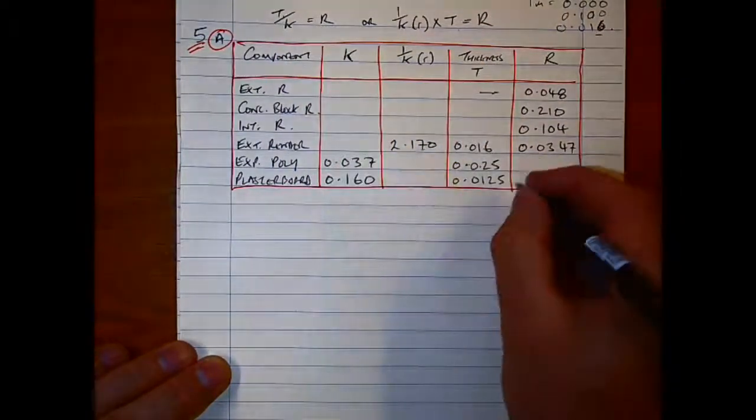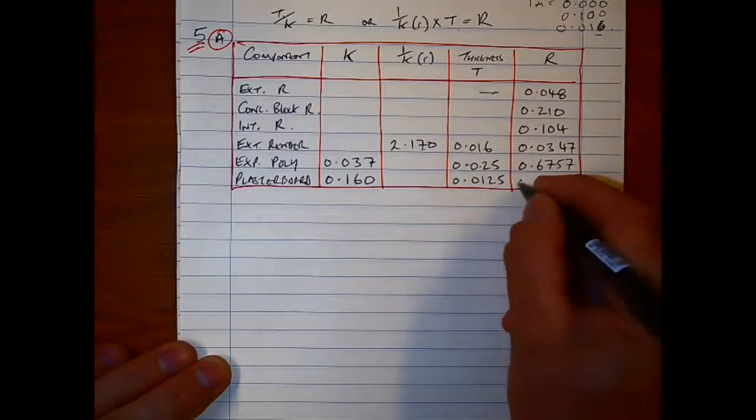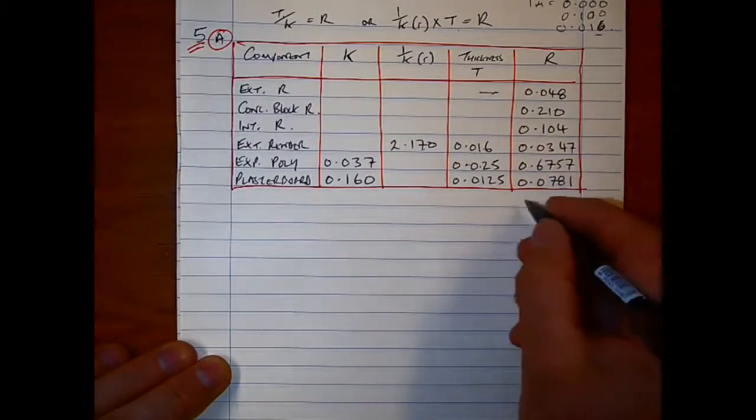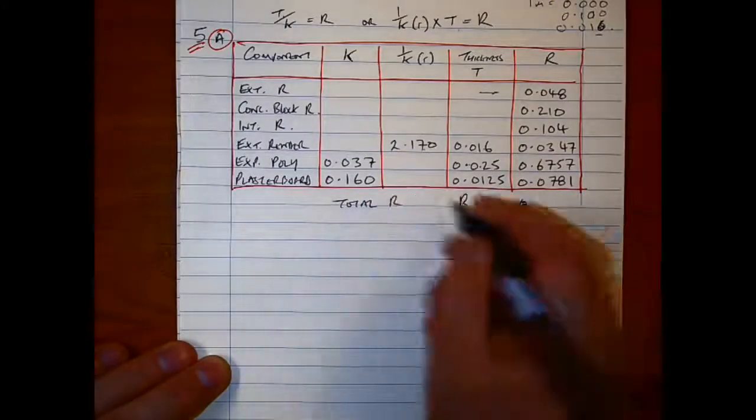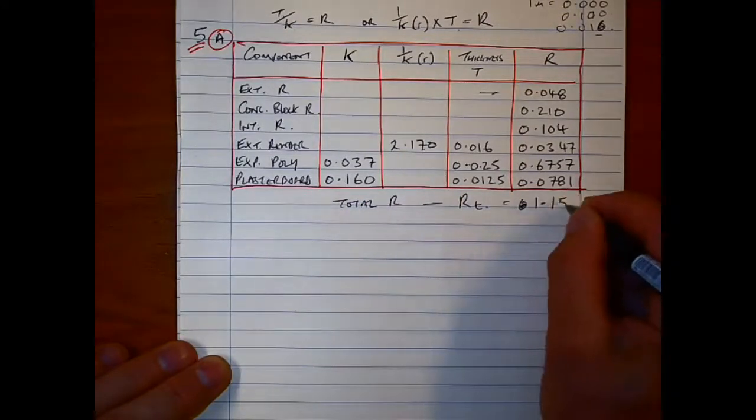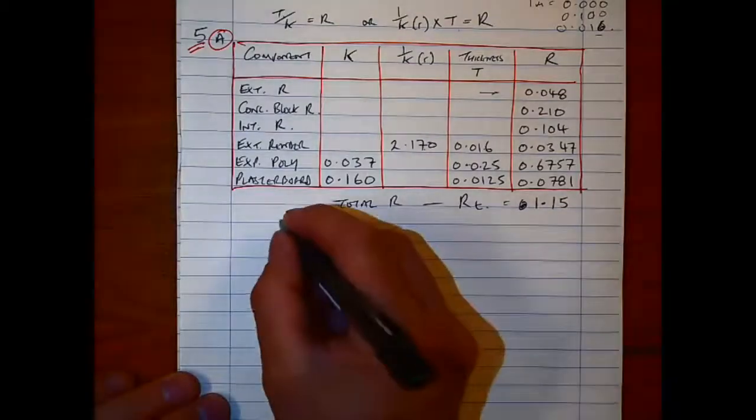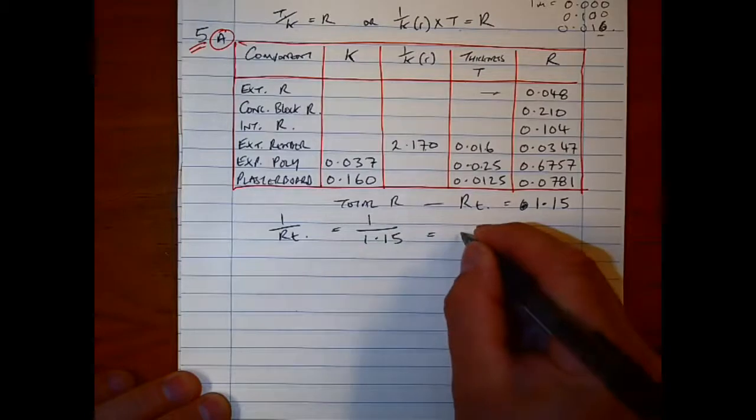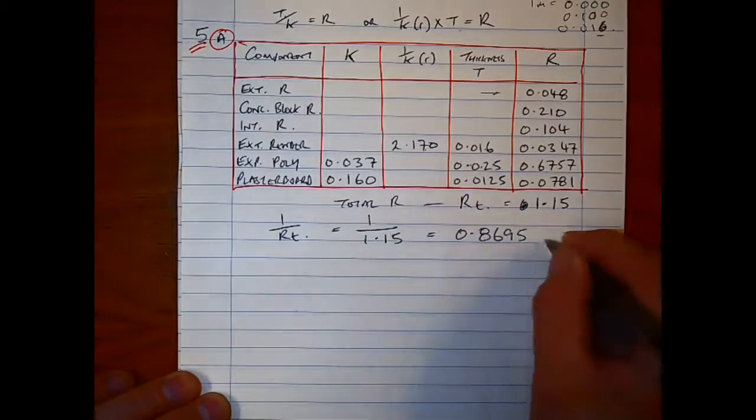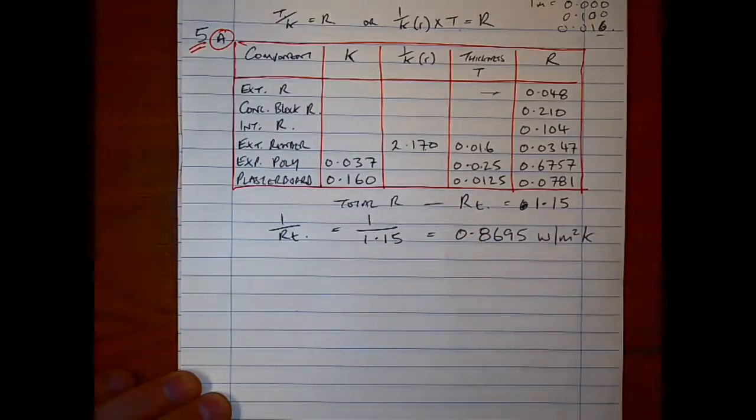So to start off with, here are the two formulas: you're multiplying the resistivity by the thickness, or you're dividing the thickness by the conductivity as shown above. I haven't done it on the calculator here just to speed things up, as I've done in other videos. It's easy enough to follow. Add up your total R, and then 1 over total R, or RT, is going to give you your U-value.